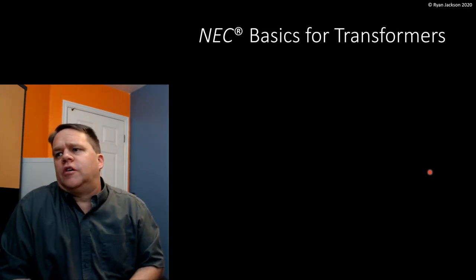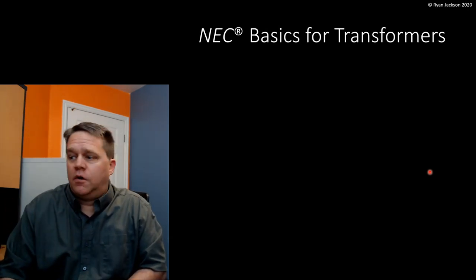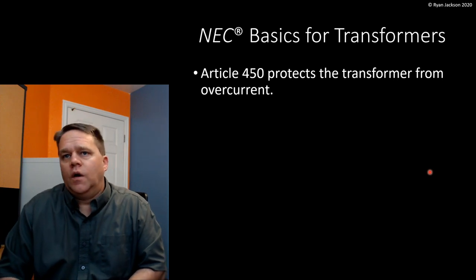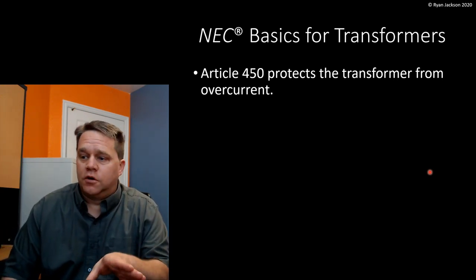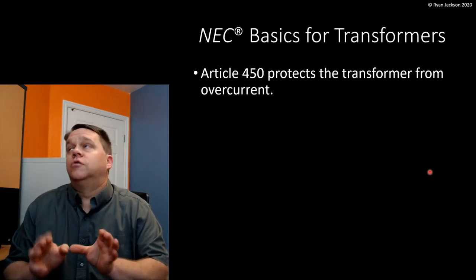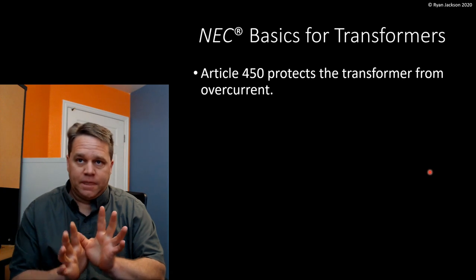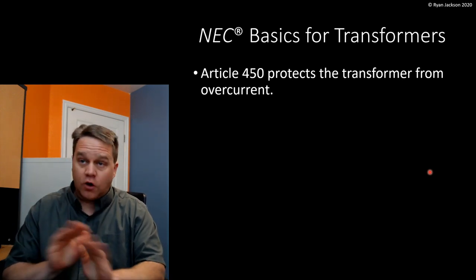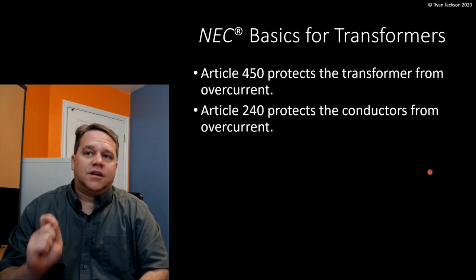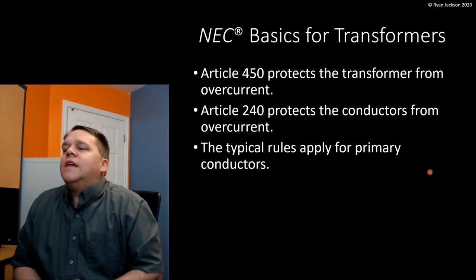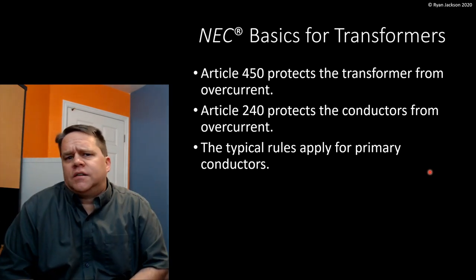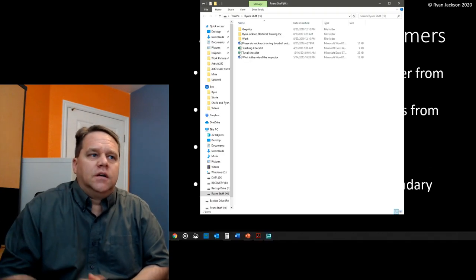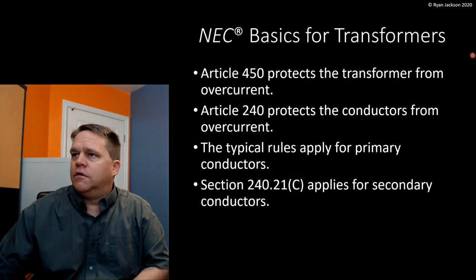Let's get into some code rules. Article 450 protects the transformer from overcurrent — that's all it does as it relates to overcurrent protection. It protects the windings. It doesn't protect the primary conductors or the secondary conductors — just the transformer itself. Article 240 protects the conductors from overcurrent. The primary is easy — there's nothing special about protecting transformer primary conductors. It gets more involved when it comes to protecting secondary conductors from overcurrent.